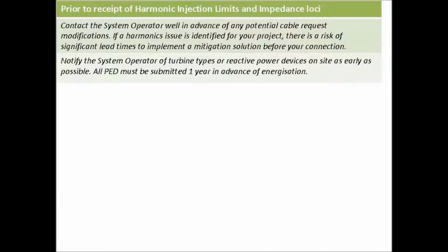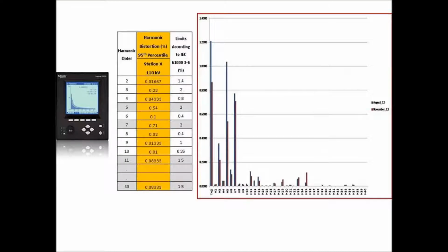Normally we have a requirement that all pre-energization data, whether it be for harmonics or dynamics or whatever else, is submitted in advance of registration or energization, at least 1 year. In this case, for harmonics, you're better off coming as soon as possible, because some of the solutions can have long lead times. So, to identify the problem in the first place, we have power quality meters scattered across the system. At each station, it records the harmonics over a week-long period in 10-minute time frames, and then we work out the 95th percentile and make sure it's below the IEC standard. So we've got a recording with the typical values, and beside it the IEC limits. They're all below it. If they start to get above it, then you've got problems.